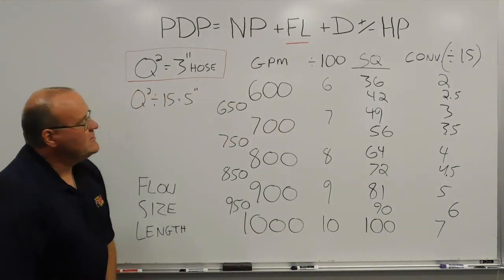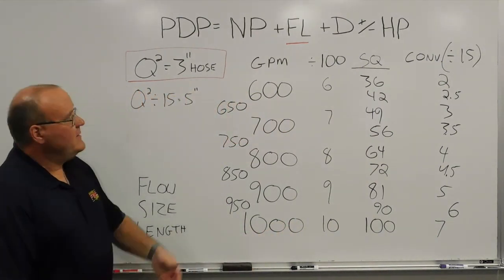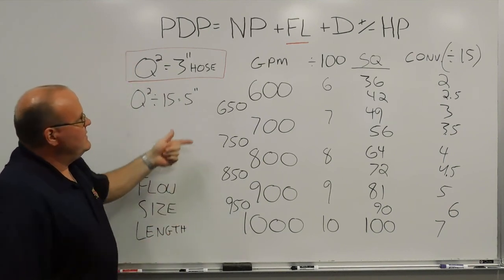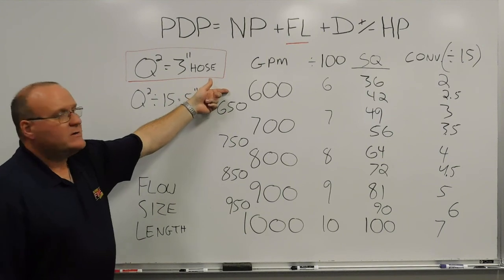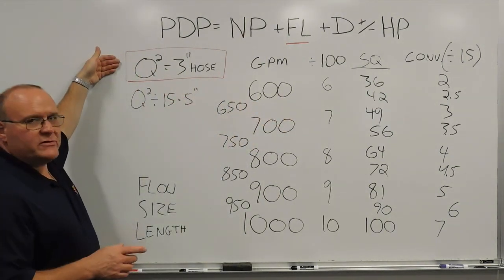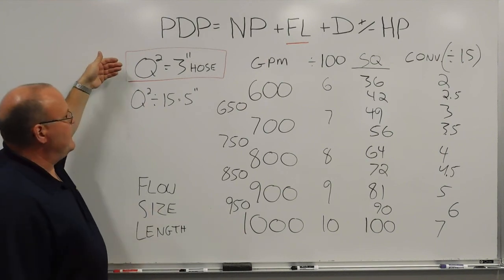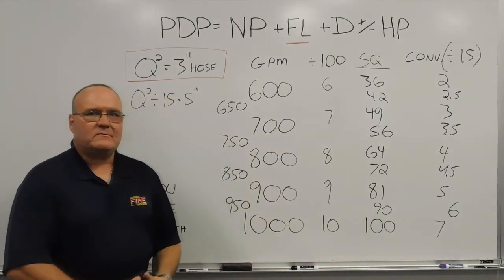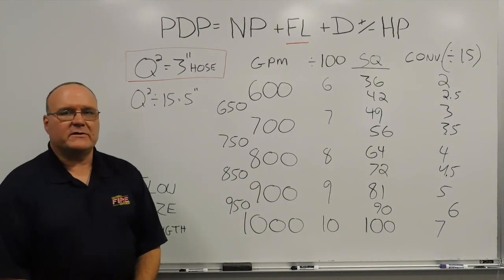So, conversion factor for 5 inch hose, starting with the 3 inch hose method, the Q squared, the hand method, gallon per minute divided by 100, square that number to get 3 inch hose. And then conversion factor for 5 inch hose is to divide that by 15. And you end up with the friction loss there. That's today's training minute for hydraulics. Thank you.